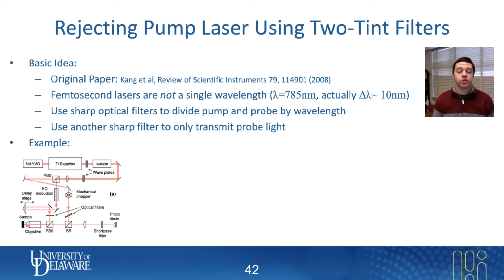And that's especially true if you have a rough sample where the light that's coming back from the sample may be losing the polarization information as it reflects back. So in those situations, you need more. And so David Cahill's group back in the late 2000s developed a technique called the two-tint technique, which is the basis for the name. Basically, it is a set of optical filters that helps distinguish the pump and probe beam not just by polarization but also by wavelength.